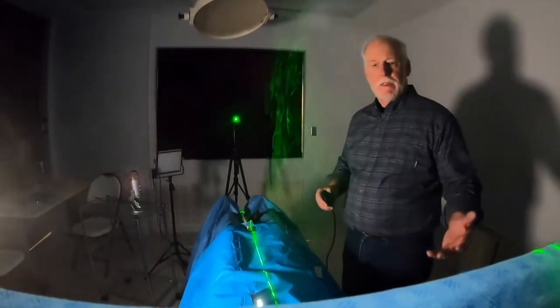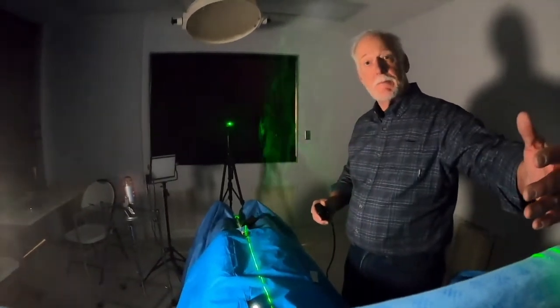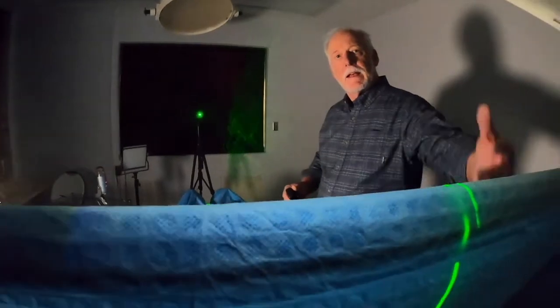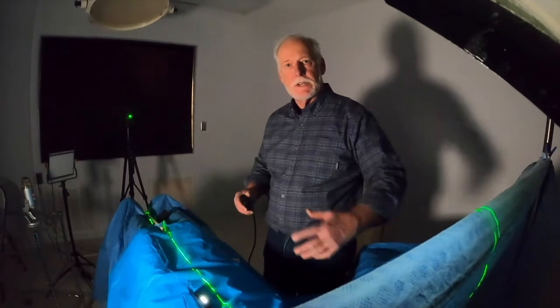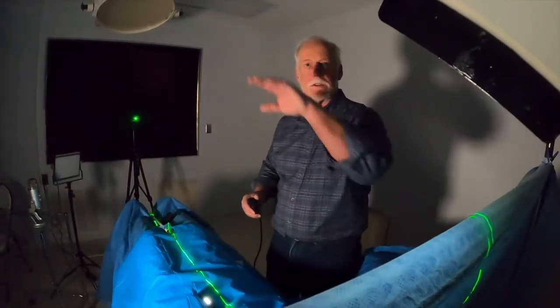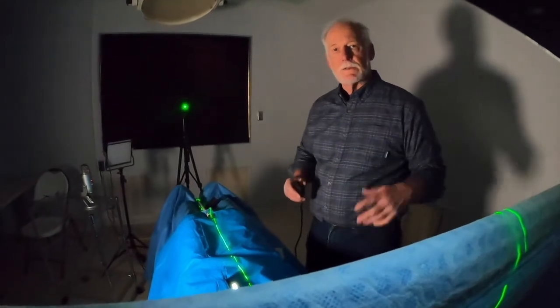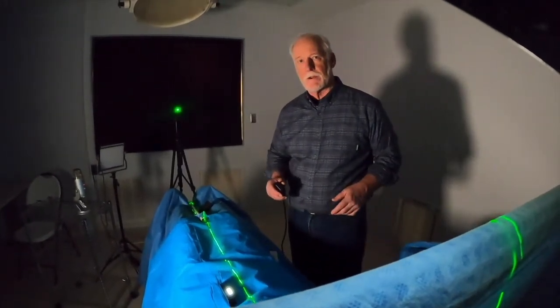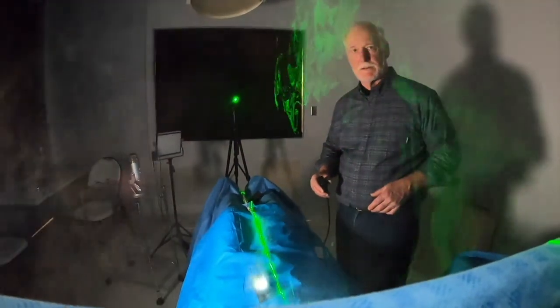How does it get there? The heat from the forced air is escaping — it goes up the back side of the grate where you're standing right now. It comes under the light, and because once it gets under the light, the energy in that heat forms a vortex in conjunction with the laminar flow coming down on this side. So it's really the waste heat from forced air warming that allows that vortex to form and all of the bad things that happen because of it.